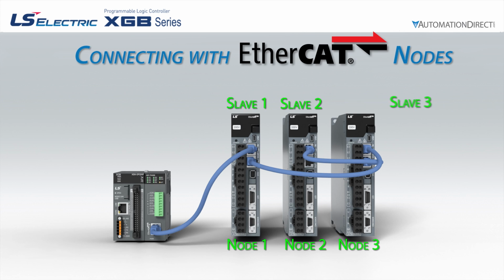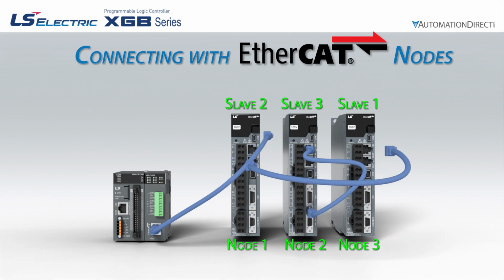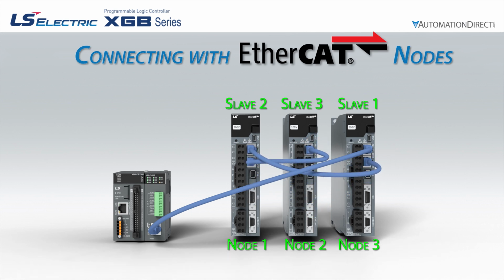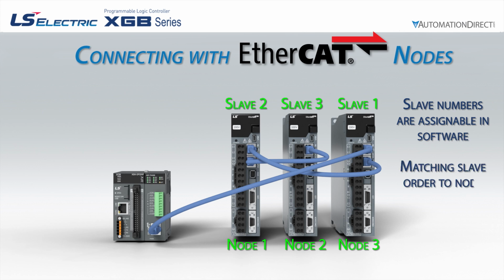If we had slave 1 mapped to node 3, slave 2 mapped to node 1, and slave 3 mapped to node 2, then the physical wiring would have to have node 3 first in line, then node 1, then node 2. This is one final physical security feature to prevent motion going to the wrong physical axis, potentially avoiding personnel injury or equipment damage. We strongly recommend you utilize this feature in your EtherCAT network.